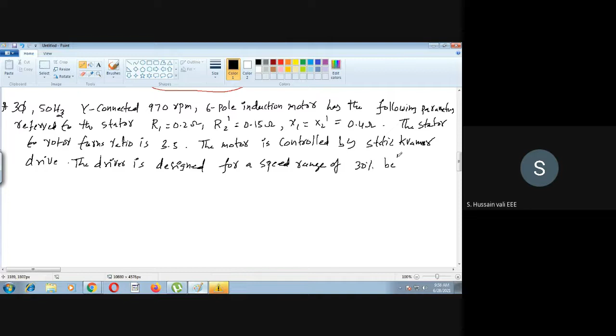The drive is designed for a speed range of 30% below the synchronous speed. The maximum value of firing angle is 170 degrees. Calculate the following.